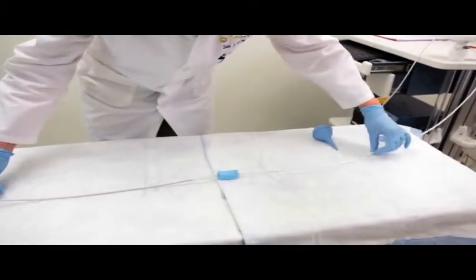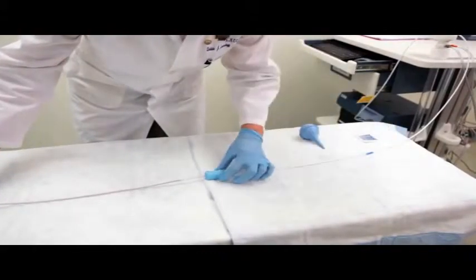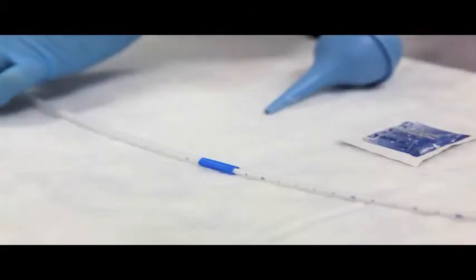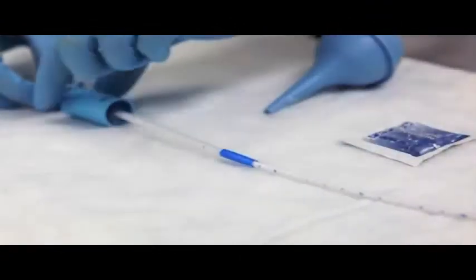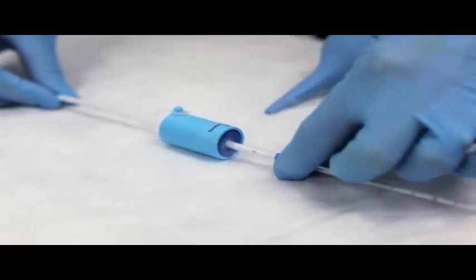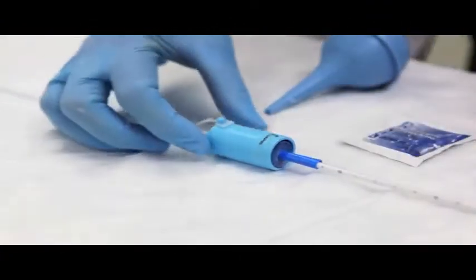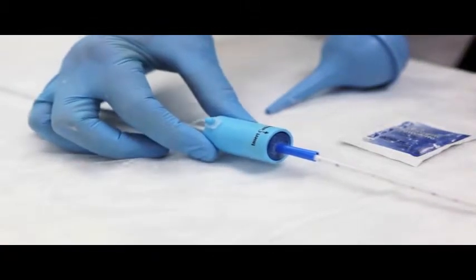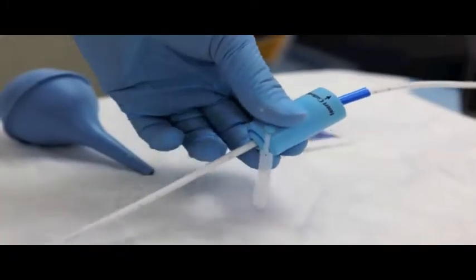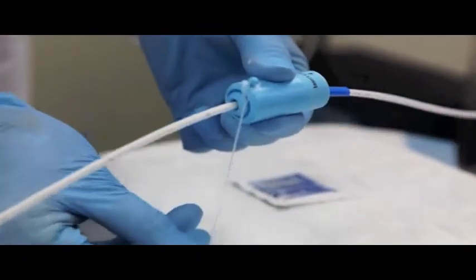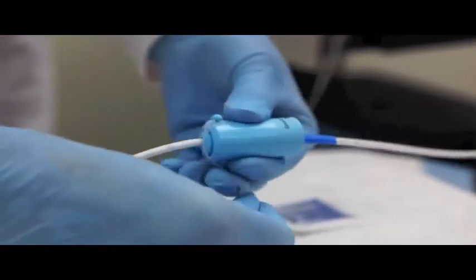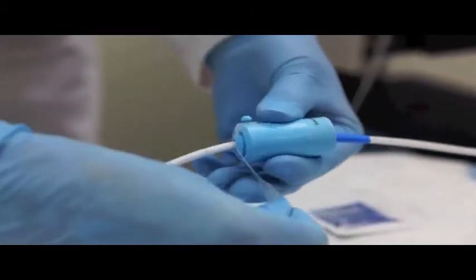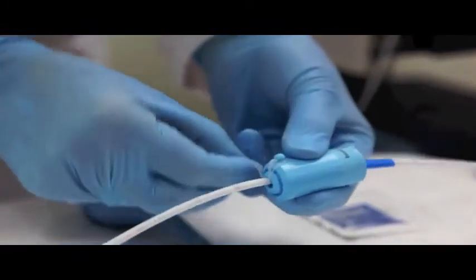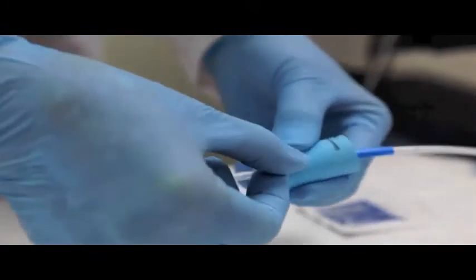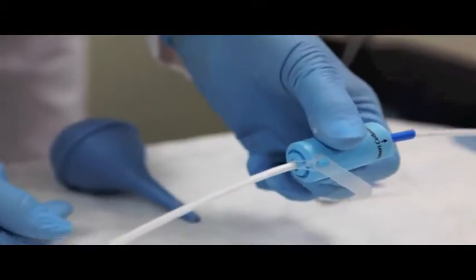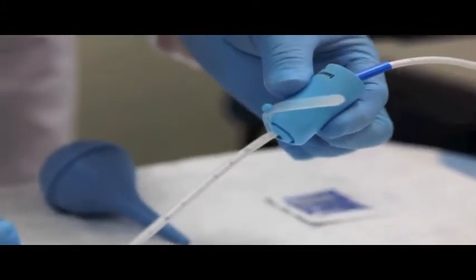Straighten out the sheath if it bunches up, then proceed with the slider. Warning: do not move the slider past the blue cuff of the sheath. If the slider passes the blue cuff, the sheath and slider must be removed and reapplied. Holding the blue part of the slider, grasp and stretch the silicone tab and wrap it 3 times around the catheter and bottom of the slider, and secure as closely as possible to the blue cuff by inserting the hole in the tab over the peg button on the slider.